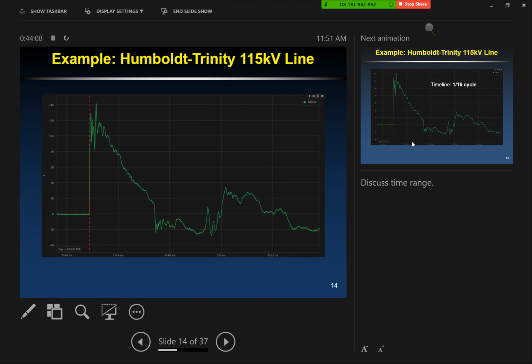It's really best to do a traditional fault location or just look at the relay. The relay is saying it's 20 miles down the line—that's kind of your starting point. So I would know ahead of time, well, what does 20 miles look like? Oh, it's around here, that looks pretty significant to me, not this. But you will see a lot of noise in your waveform, and it all depends on where the reflections are coming from. You could have reflections coming from behind you, bouncing off of transformers or distribution feeders coming in.